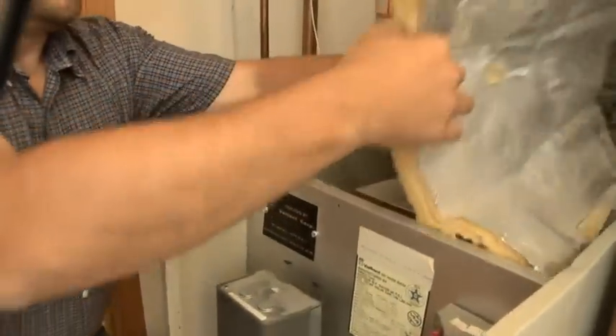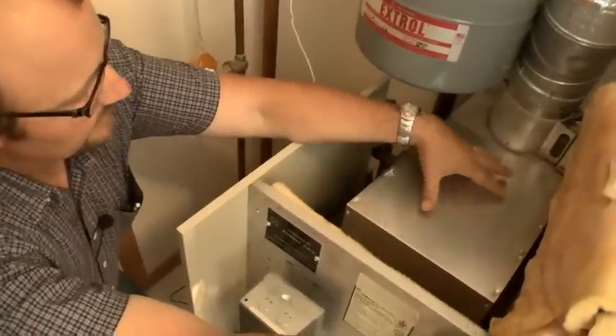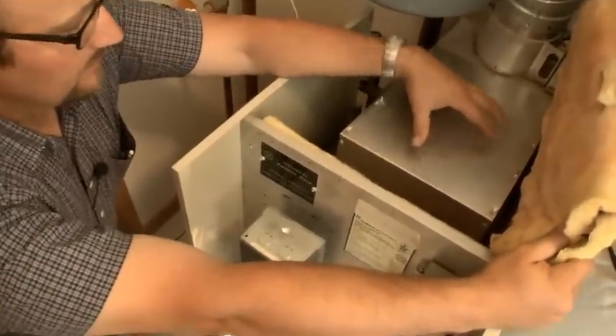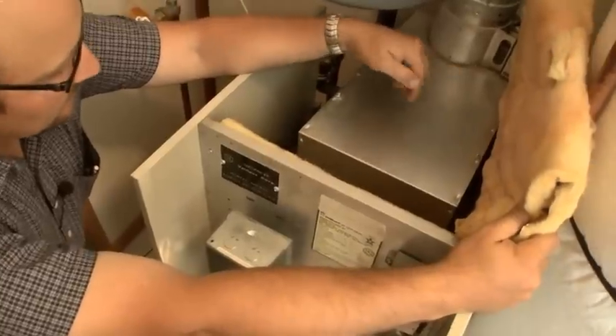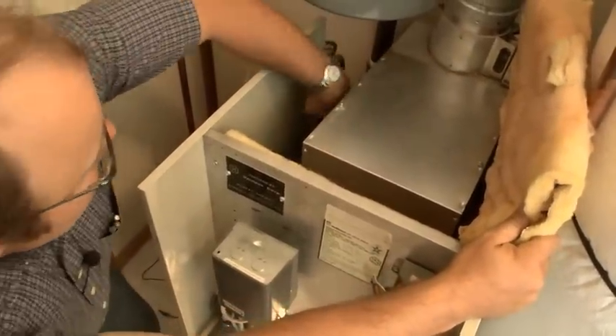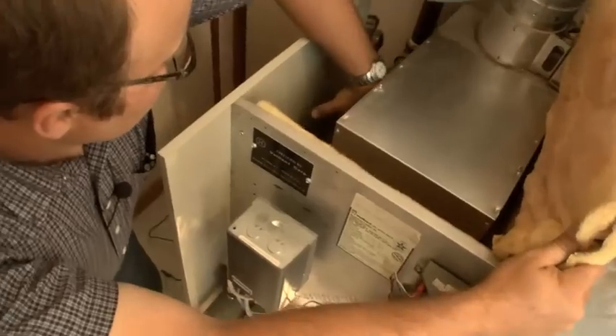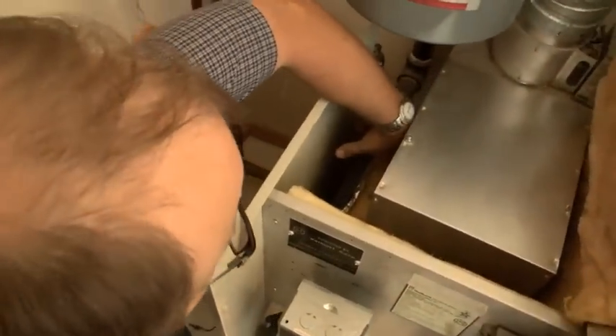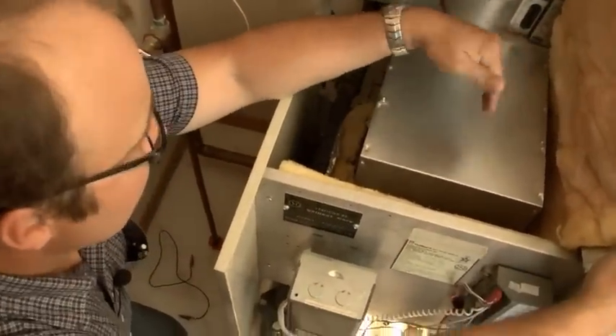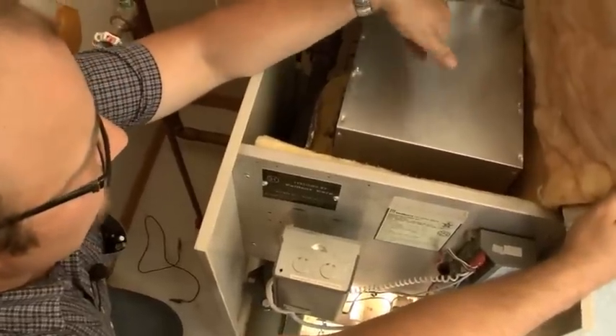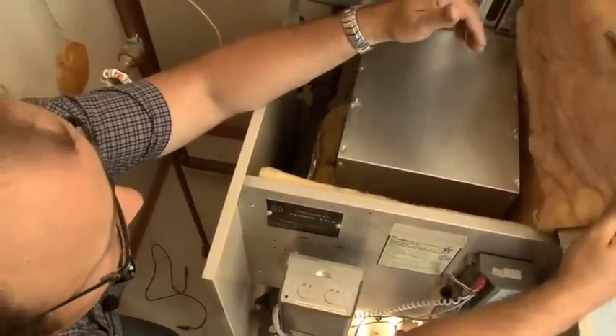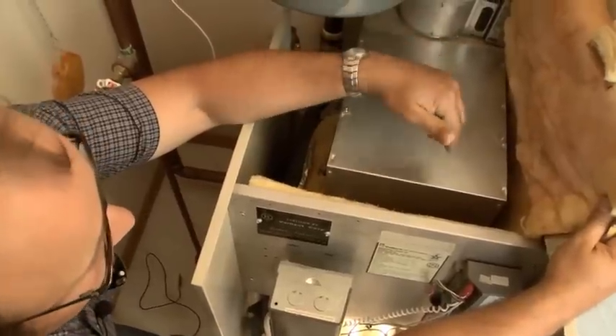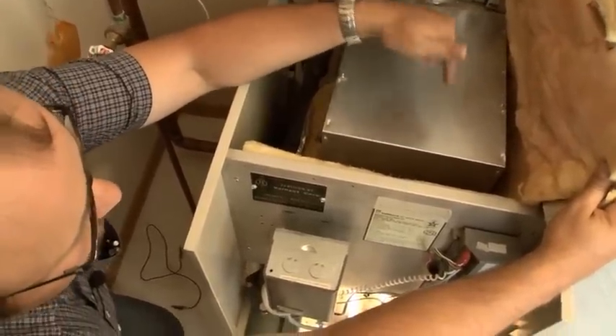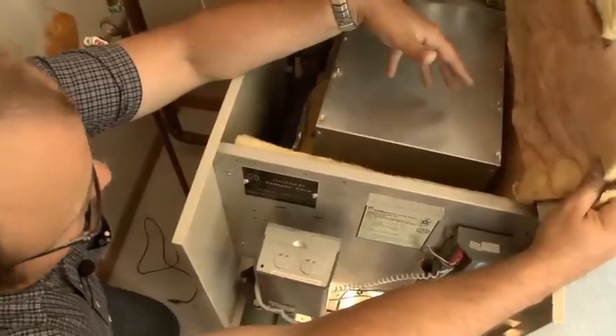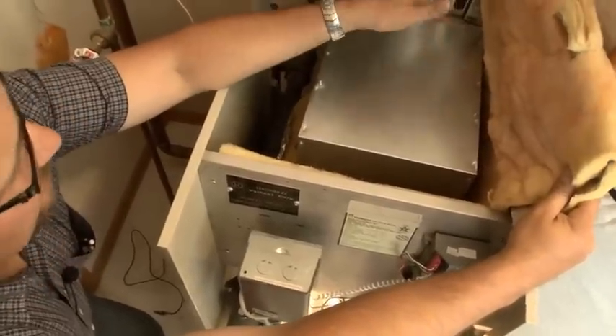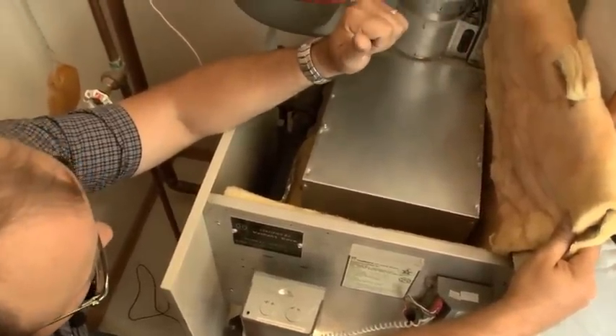This is part of our flue gas collector right here. And what you do is you remove this top piece, and then you can look down into the heat exchanger. Okay, here's the heat exchanger down here. You can remove this top piece, look down into the heat exchanger, see the openings where the flue gases come up through. If that is dirty and sooted, then you use a brush and you brush through there and clean that out so that the flue gases can rise up through the heat exchanger nice and easy.